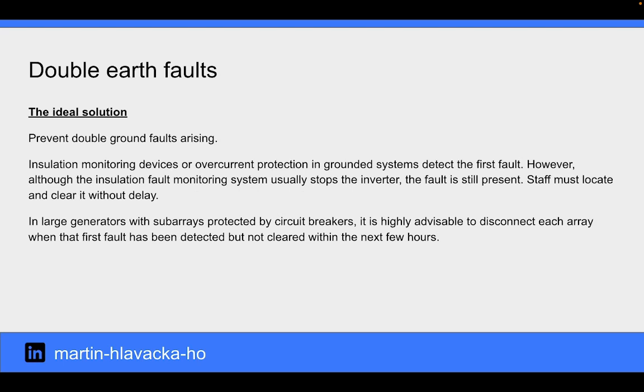The ideal solution is to prevent double ground faults arising. Insulation monitoring devices or overcurrent protection in grounded system detect the first fault. However, although the insulation monitoring system usually stops the inverter, the fault is still present. Staff must locate and clear it without delay. In large generators with subarrays protected by circuit breakers, it is highly advisable to disconnect each array when the first fault has been detected but not cleared within the next few hours.